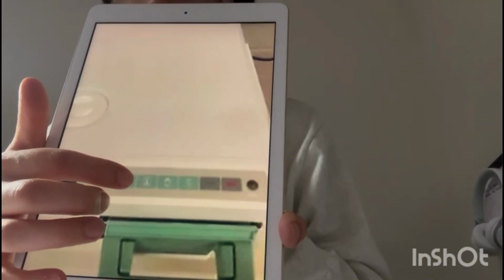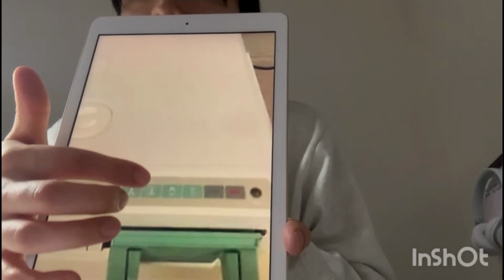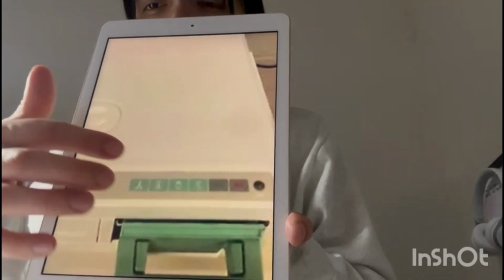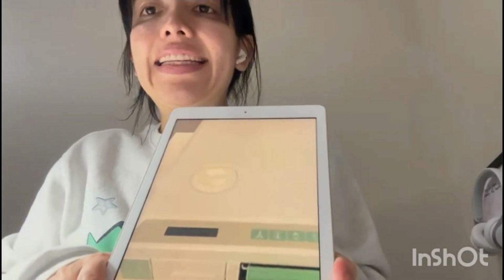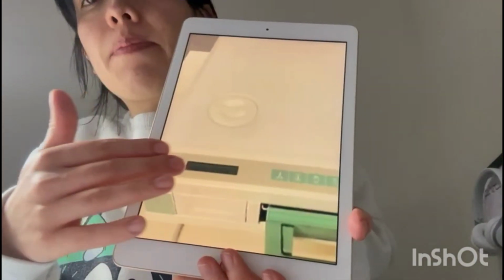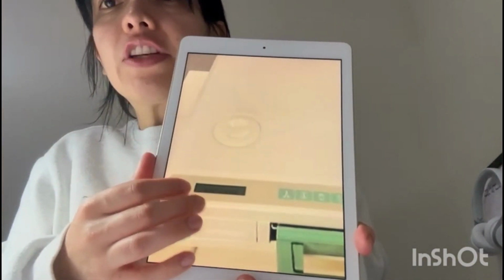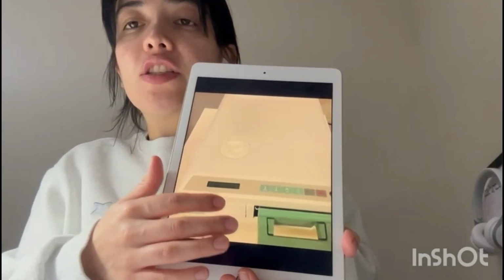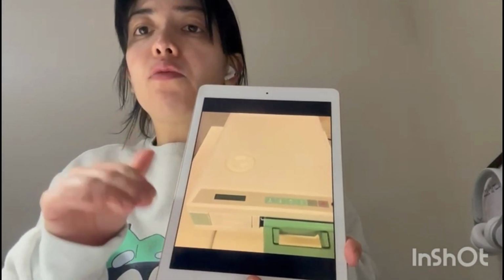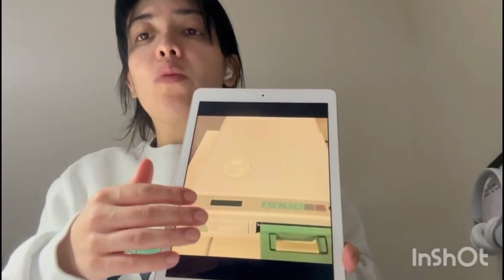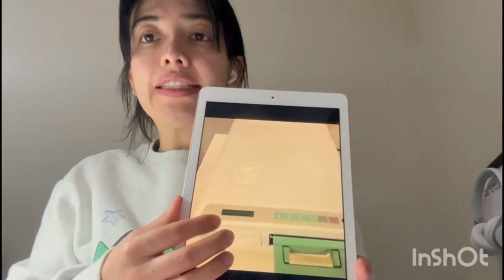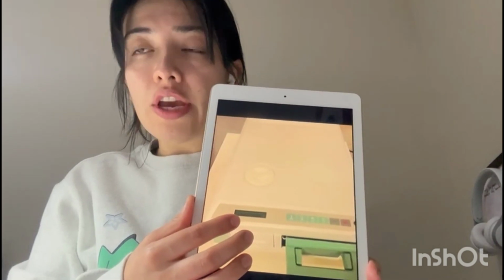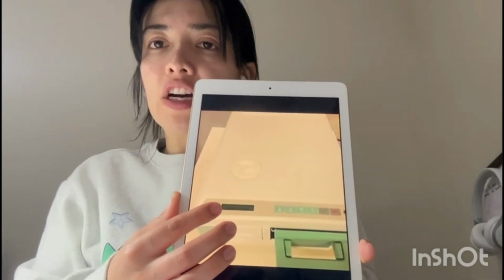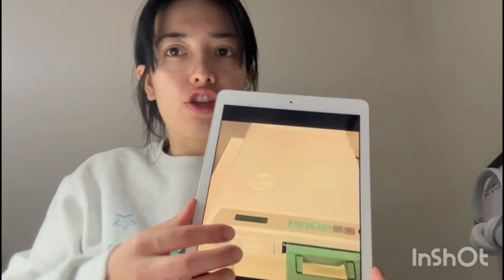This is the panel where we are going to select the correct load, if it is wrapped instruments, and we're going to select start. On this panel, we are also able to see if the machine is going through any error. The machine will shut down by itself and let us know in this panel that it is having some issues, and we can find more information about the issue in the manufacturing instructions.